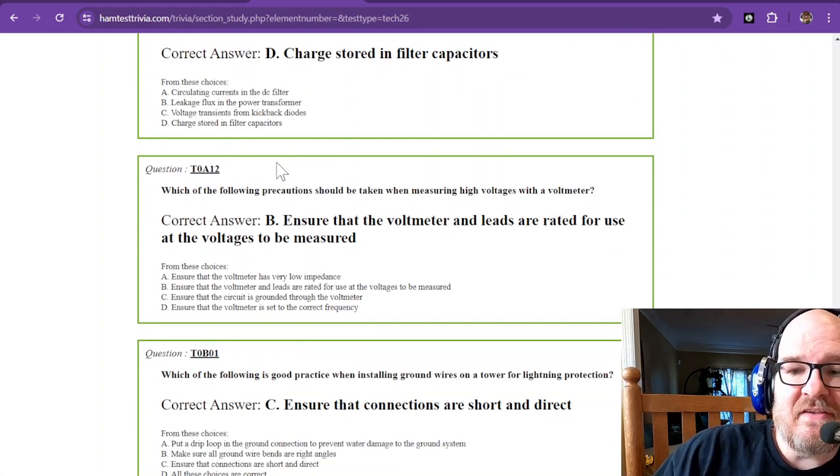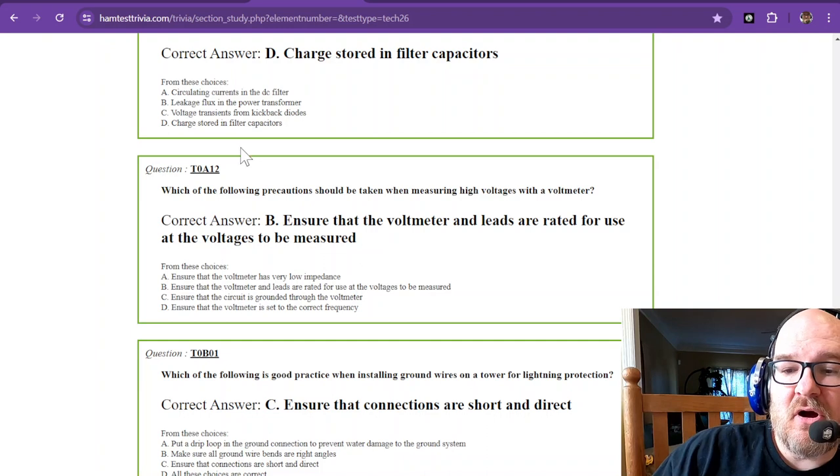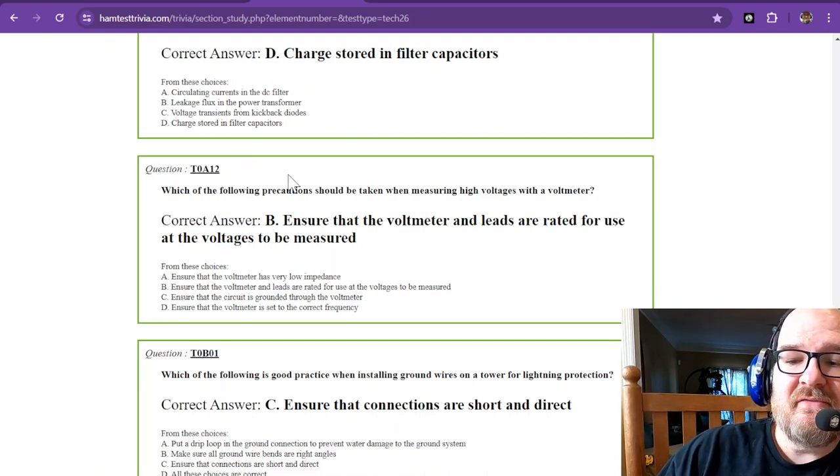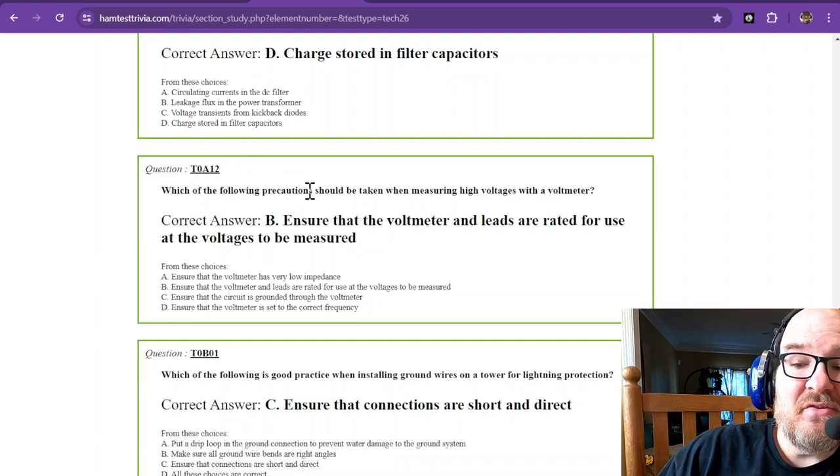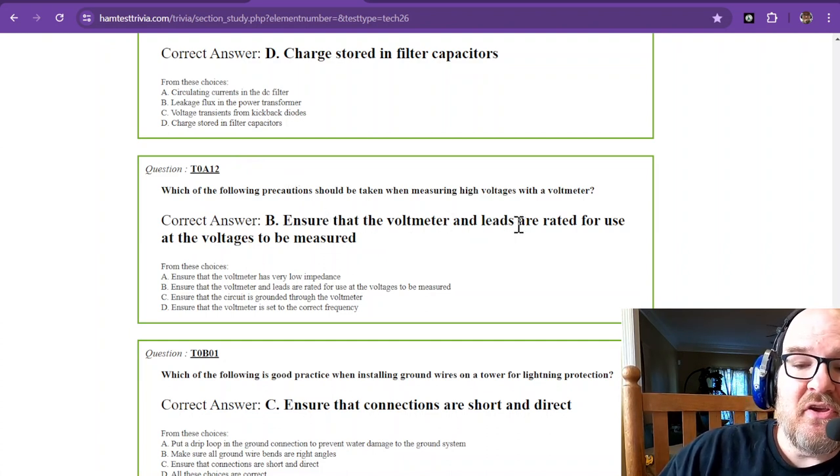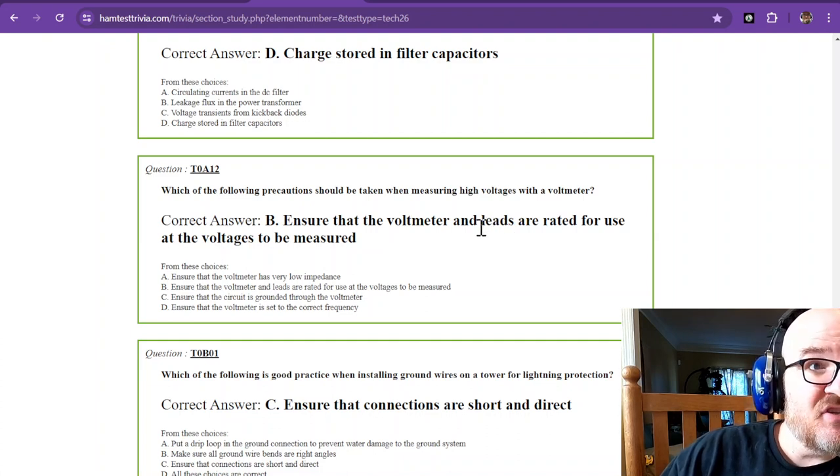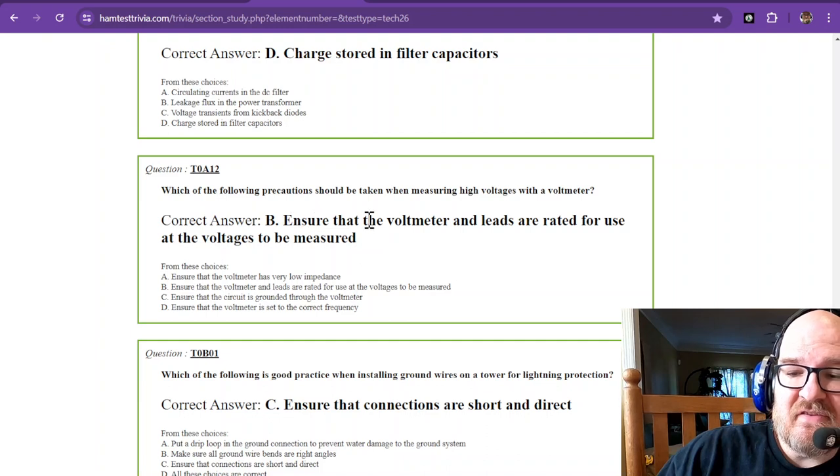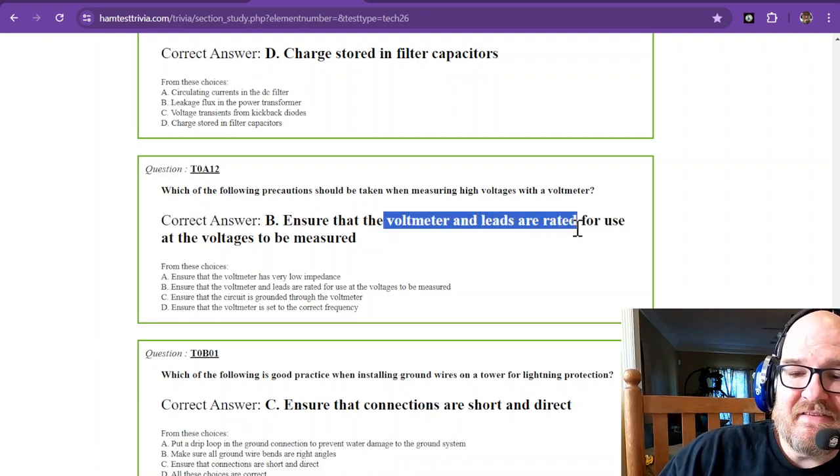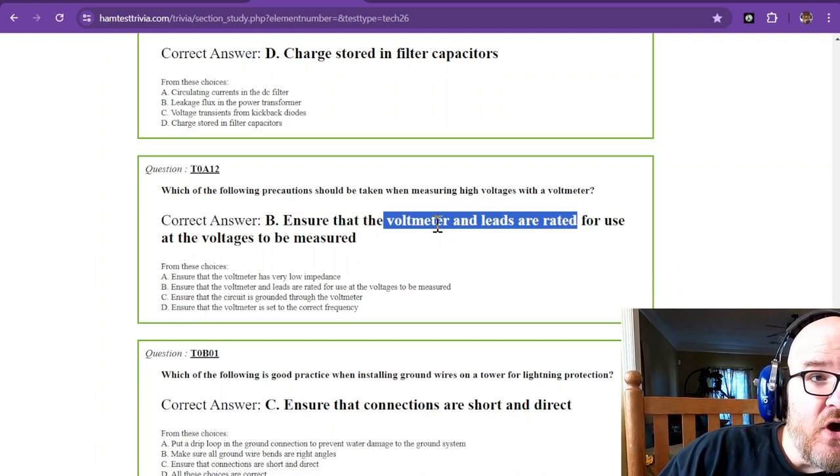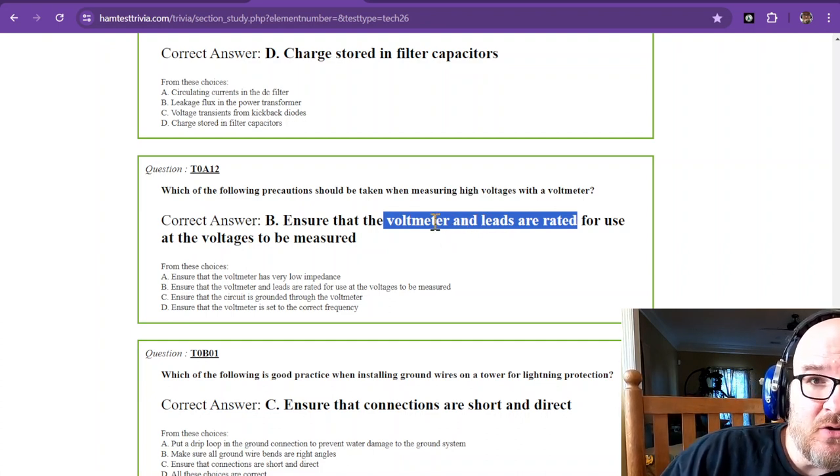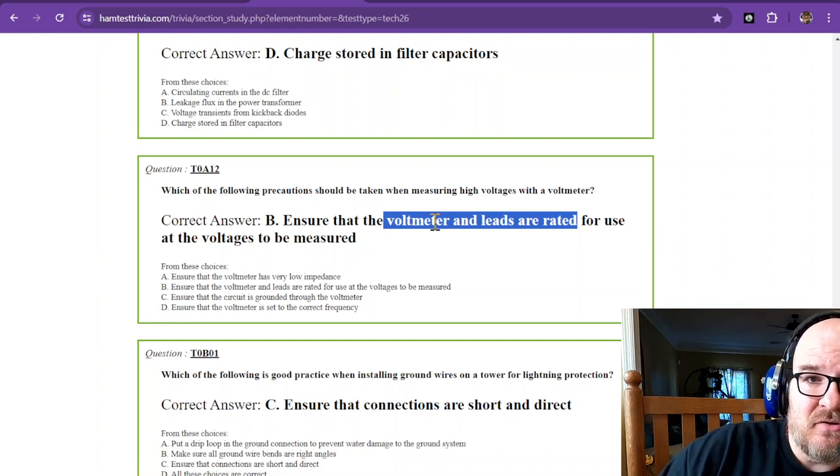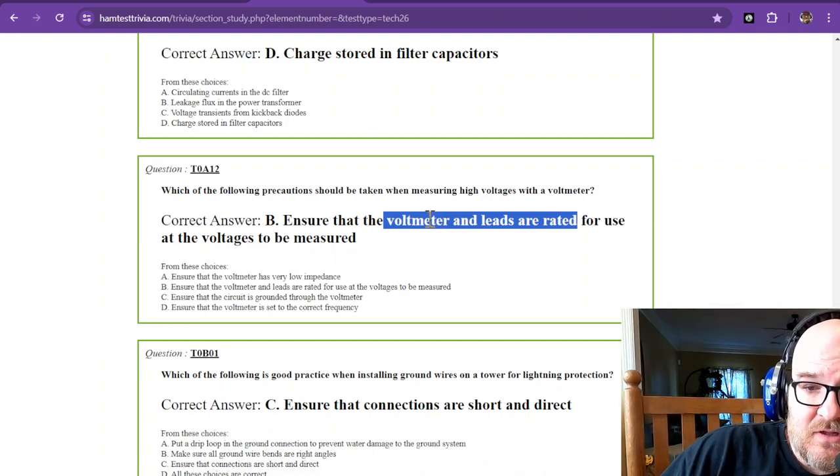Which of the following precautions should be taken when measuring high voltages with a voltmeter? You need to ensure that the voltmeter and leads are rated for use at the voltages measured. The voltmeter and the leads need to be rated for use at those voltages. Don't go using one of those cheap little $5 meters to measure a 480 volt system. You'll be sorely disappointed.